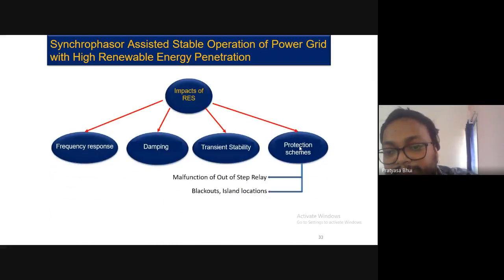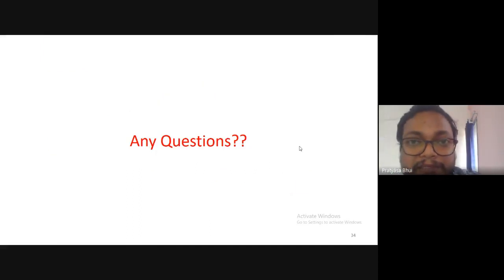In the protection schemes, sometimes out of step relays will malfunction. As you know, sometimes zone 3 and out of step relays malfunction and can create blackouts. So how to identify any error in those? Because of renewables, your system operating condition is changing. One threshold you set for one relay or protection system may not work well for all operating conditions. So how to check whether those out of step relays will work properly or not for all conditions? So I have completed the presentation.